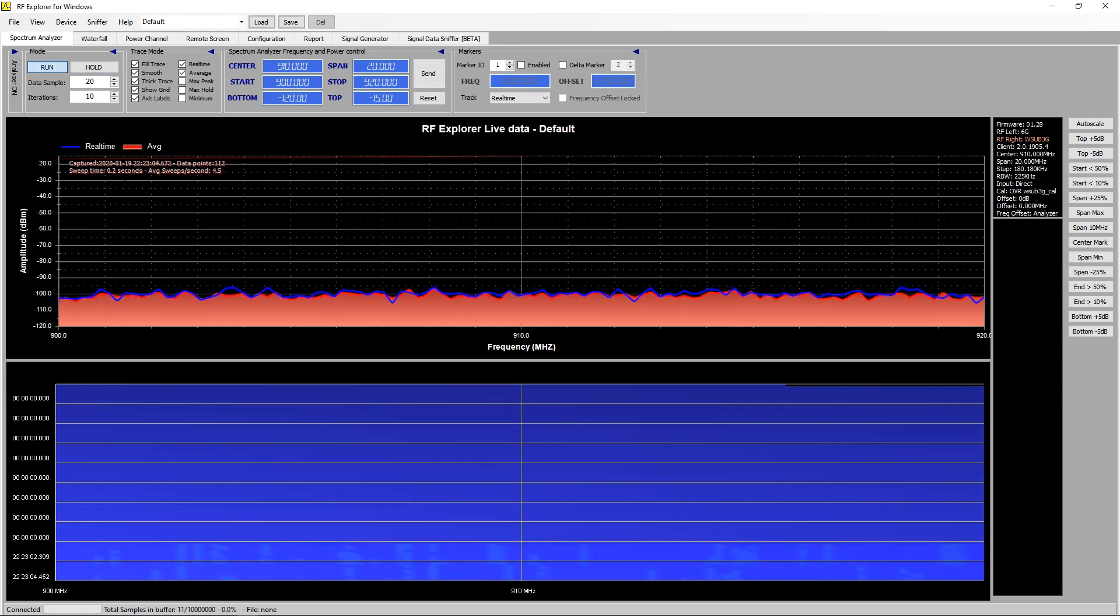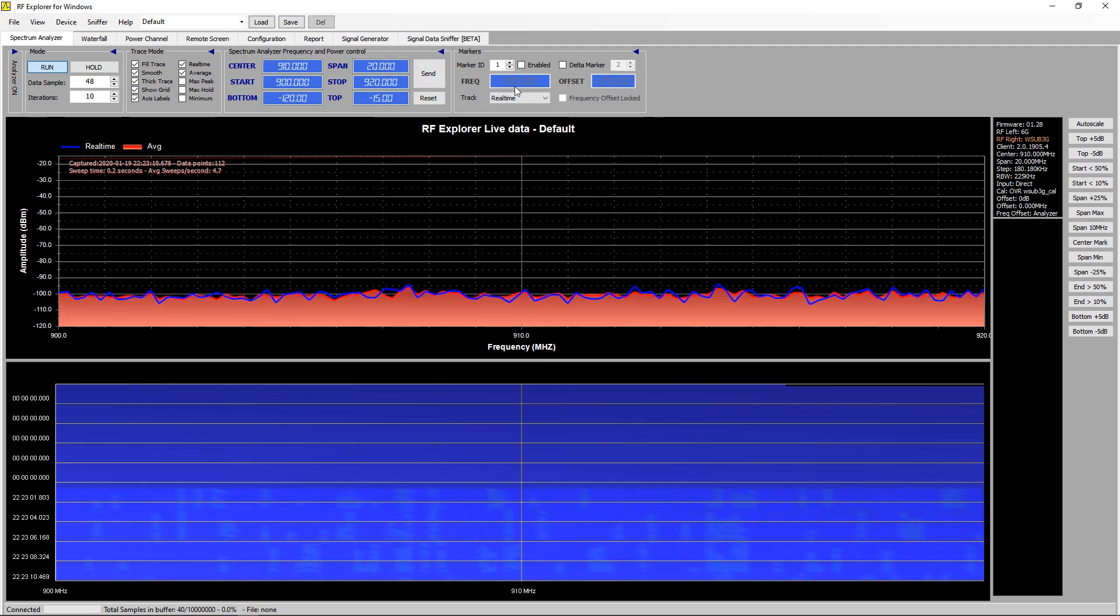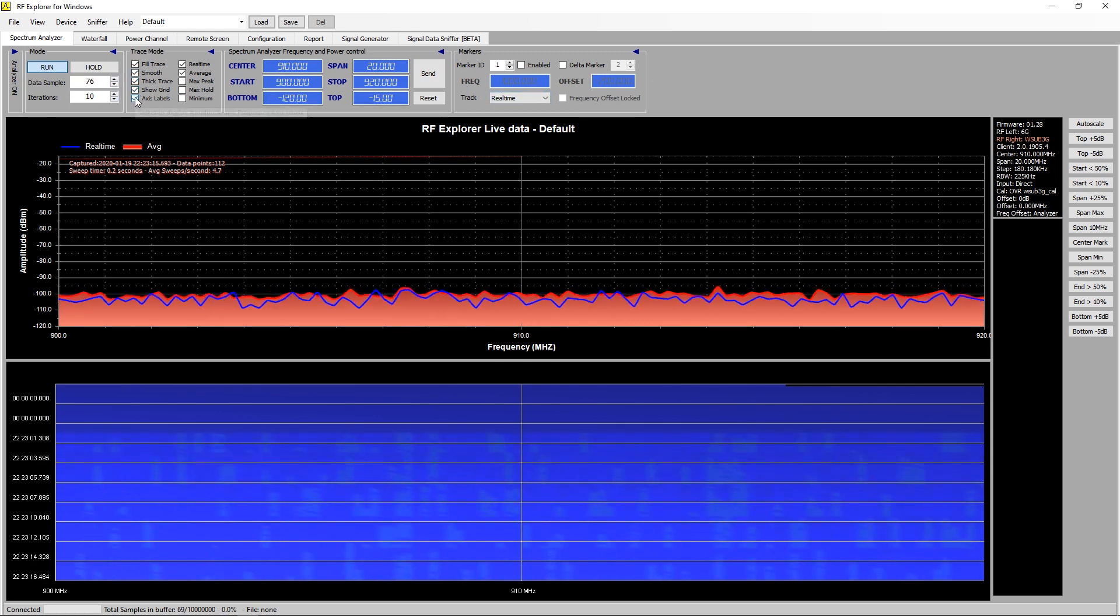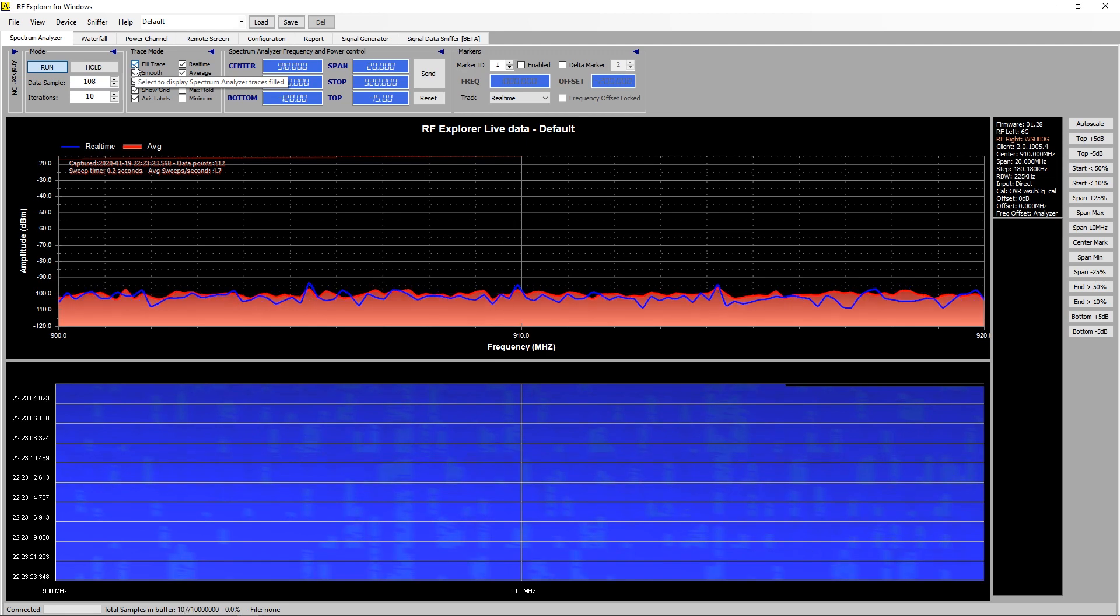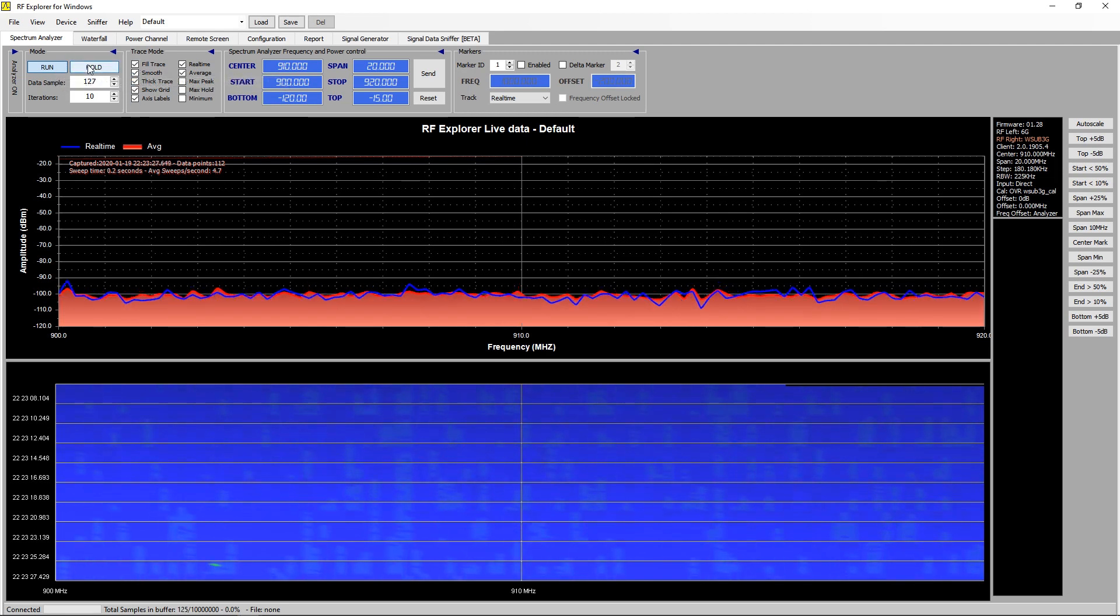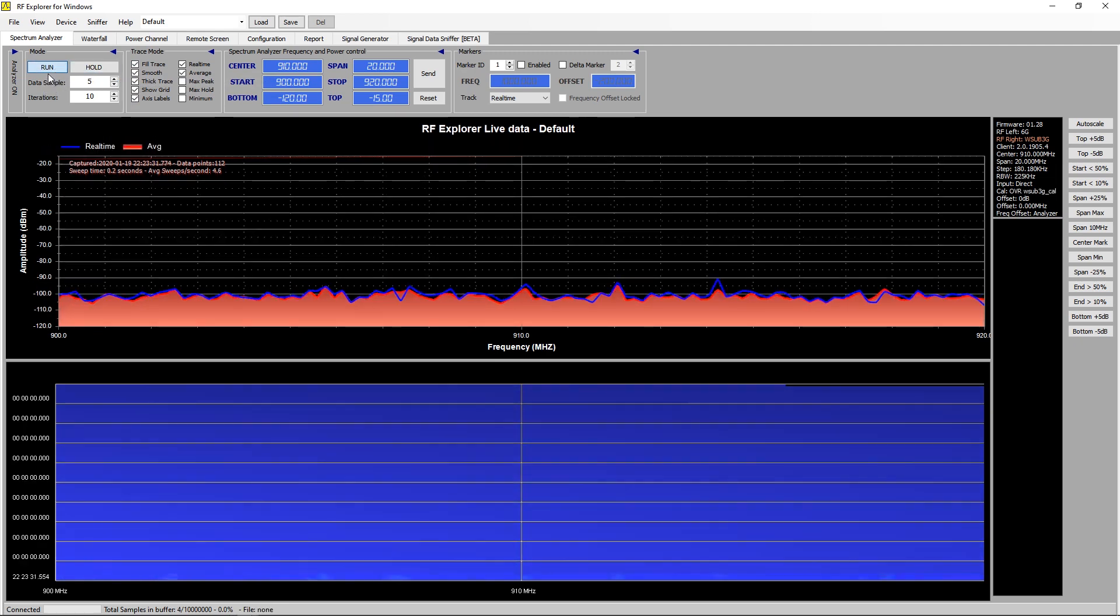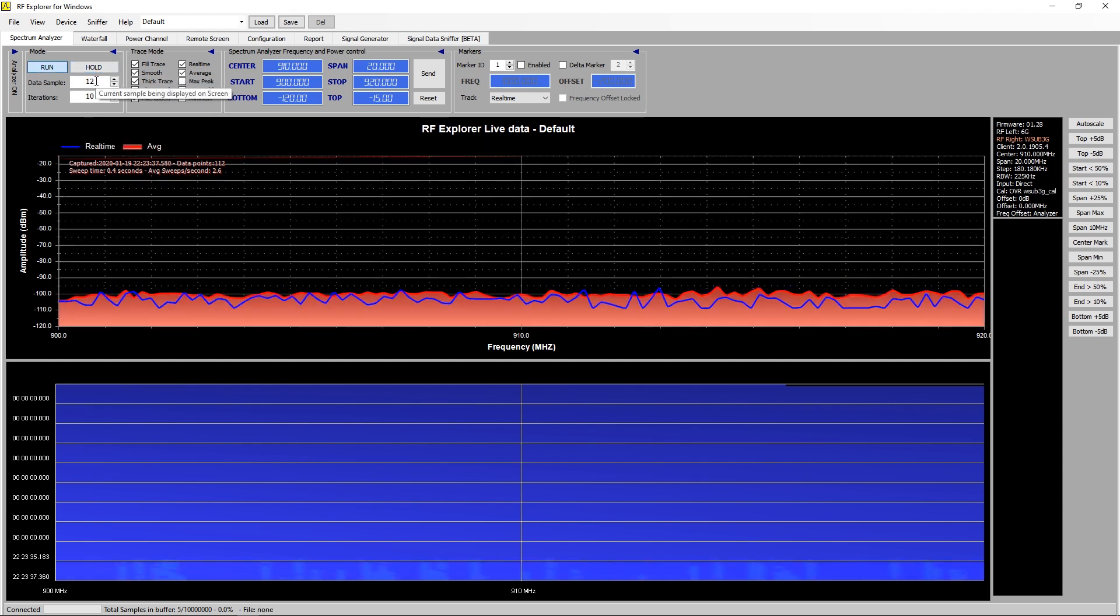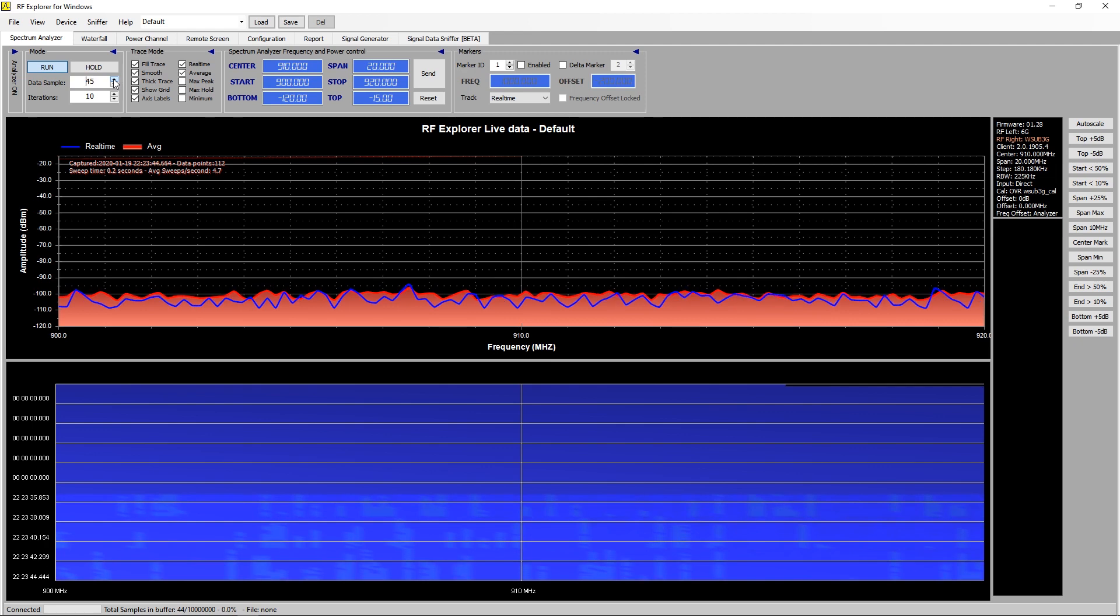Once that's happened the unit will spring to life. Along the top here, this is like the toolbar. This gives you quite a lot of information and it's quite crowded at the moment. We'll start turning some things off. First of all this is run, this is hold. If I click this it will stop it. I can hit hold and it will actually hold it and then start again. This gives you the sample rate - you can increase or decrease it so that you get a slightly better resolution or a more lively display.